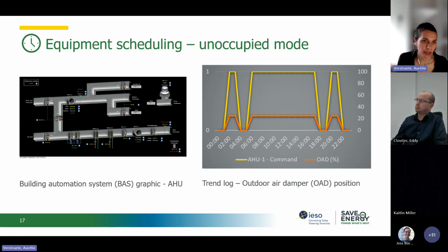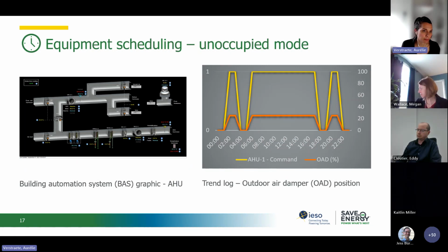Then maybe for the second air handling unit in that building, you see that it is on automatic mode. So here it is authorized to run during unoccupied hours for night setback, for example, to maintain 18 degrees indoor, which is totally okay. But then, reviewing trend logs, you see that the outdoor air damper opens at night when the building is empty, which means that you need to heat and cool outdoor air when it is not required. Here, the system should be on recirculation mode.